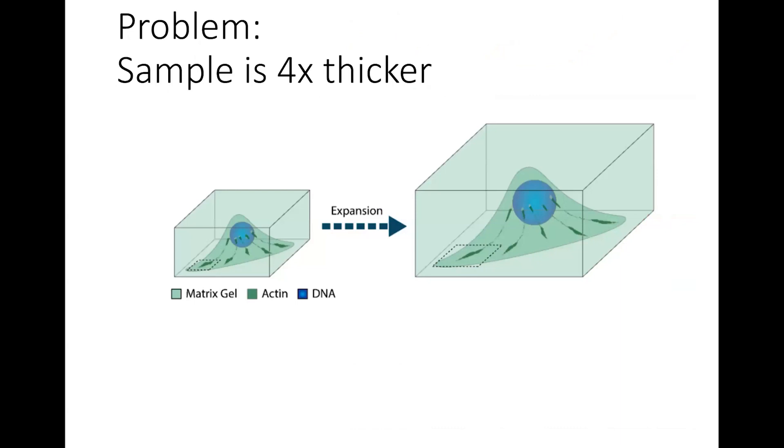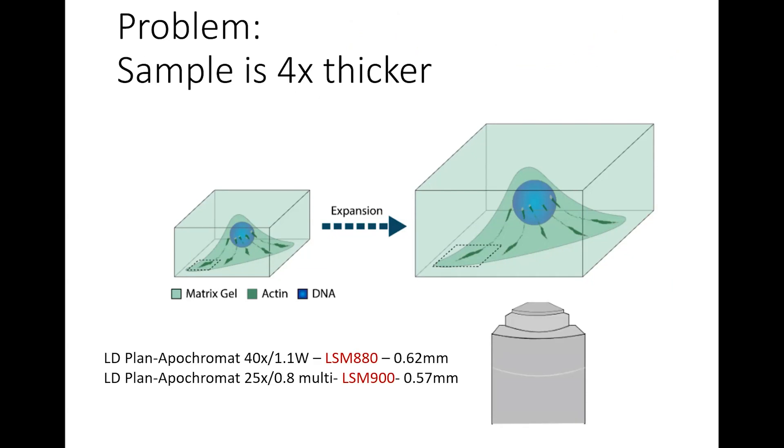Another problem that you'll run into is the expansion is in all directions, so now your sample is four times thicker. One of the keys to this is to use a long working distance objective. At HCBI, we have a 40x 1.1 long working distance water on the LSM 880, and we have a 25x 0.8 multi-immersion lens on the LSM 900 that both would work for this. Another thing that you need to make sure is if you're doing a monolayer of cells, it's key to remember to be able to track which side is up because you will not be able to image all the way through the gel.